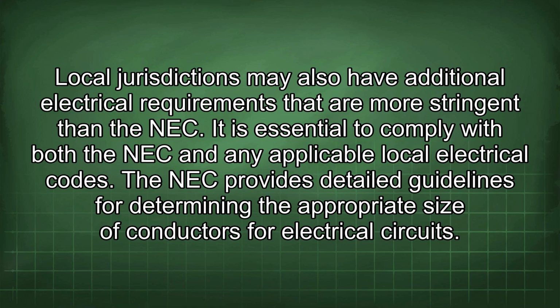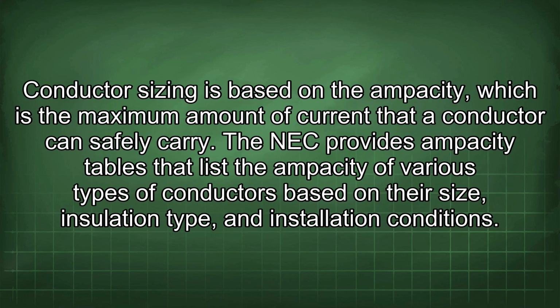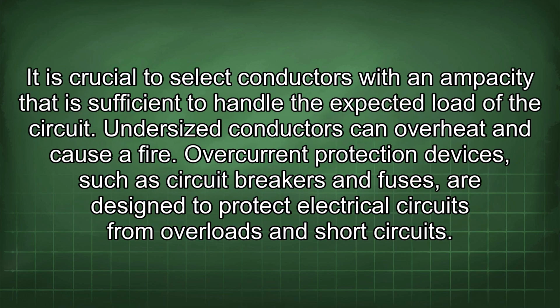The NEC provides detailed guidelines for determining the appropriate size of conductors for electrical circuits. Conductor sizing is based on ampacity, the maximum amount of current a conductor can safely carry. The NEC provides ampacity tables listing the ampacity of various conductor types based on their size, insulation type, and installation conditions. It is crucial to select conductors with sufficient ampacity to handle the expected load of the circuit, as undersized conductors can overheat and cause a fire.